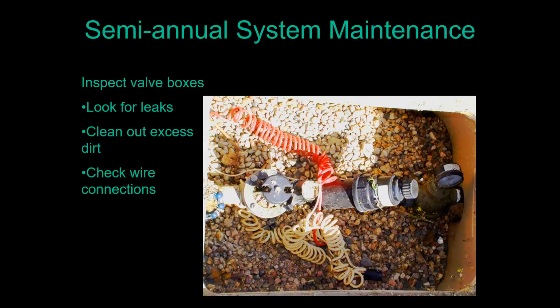So unfortunately, way too many people are using just standard wire nuts down there. And the ends of the wires inside those standard wire nuts is exposed copper. Inside your valve box, it's always damp. It's underground in a box with a lid, so there's always a good high moisture content in there, and being damp is normal. Standing water is not good. That means you do have a leak. So what you do want to use is some type of a waterproof wire connector, and I'm going to pop out of the presentation here for just a moment.